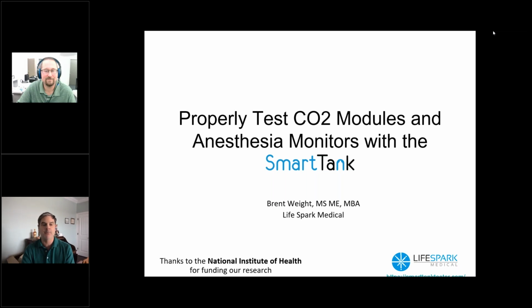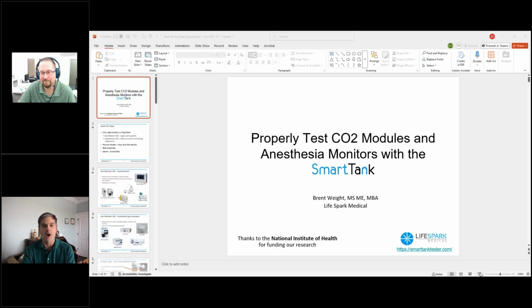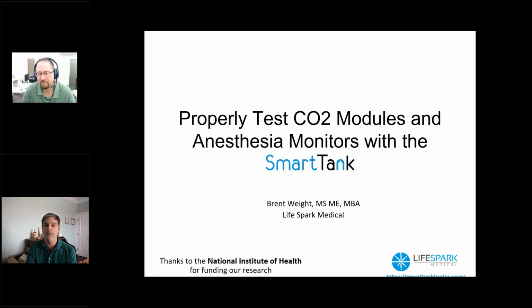It automates the testing process, delivering more accurate results in less time using less gas, all backed by detailed test reports. With its intuitive interface, the SmartTank features preloaded test sequences that guide operators step by step through the testing process. It eliminates the need for separate gas regulators, flow meters, syringes, tubes, pressure gauges, and even service manuals. All the necessary hardware is built right in. It can even assist with patient monitor testing.